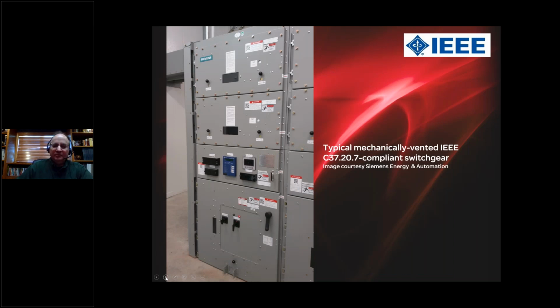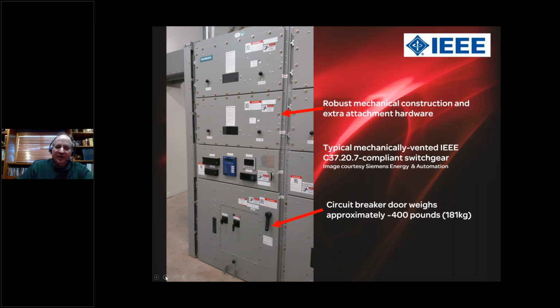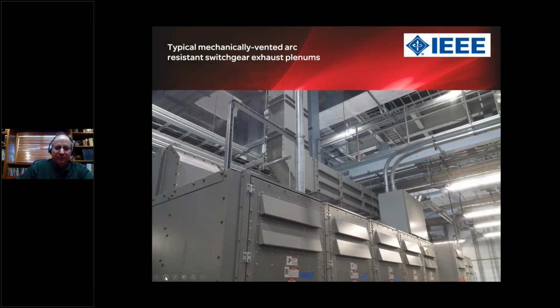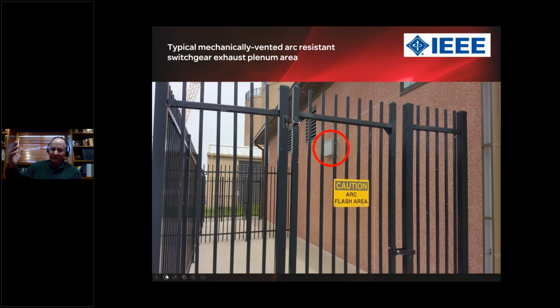So here's some typical equipment. This is 15 kV metal clad switchgear manufactured by Siemens. This is installed in a wastewater plant. Very robust construction. Look at all the bolts on each of those panels. The circuit breaker door you see at the bottom here weighs approximately 400 pounds. So extremely robust. I call it the Abrams tank approach to building switchgear. We're going to be able to contain that arc flash incident energy and vent it out the top with these exhaust plenums that you see here. And in this case, since they couldn't bring it out the roof, they exhausted it out the side of the building, because there were offices up above the area. They exhausted it out the side of the building and built fences around the area. So, of course, no one would put a picnic bench there or station themselves adjacent to an arc flash exhaust plenum.